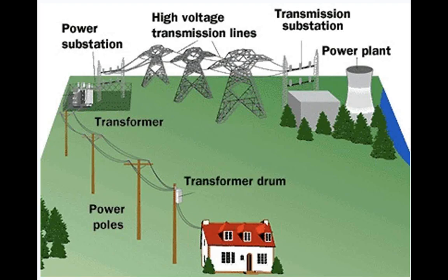So where are we in this big food chain? We start out here, we got the power plant. The power plant makes it at a low voltage, 24K typically, and it's got to step it up to move it in the transmission. It's going to step it up to what we call a transmission voltage. In Connecticut, that could be up to 345,000 volts. Out west, you can go to 500, you can see some 700 stuff. But if you see the big towers, that's just transmission voltage. Now, when a utility needs some power, they drop it out of the transmission and put it into a substation. The substation is where we step it down from transmission to what we call primary voltage.